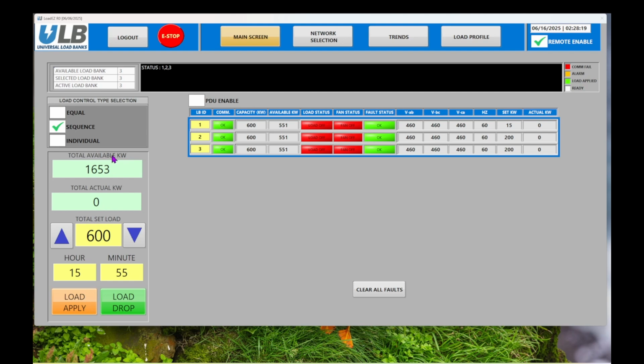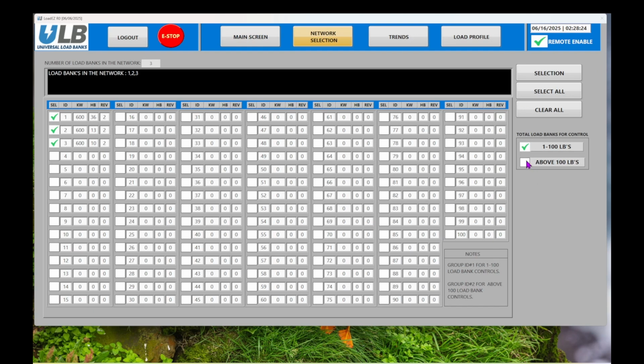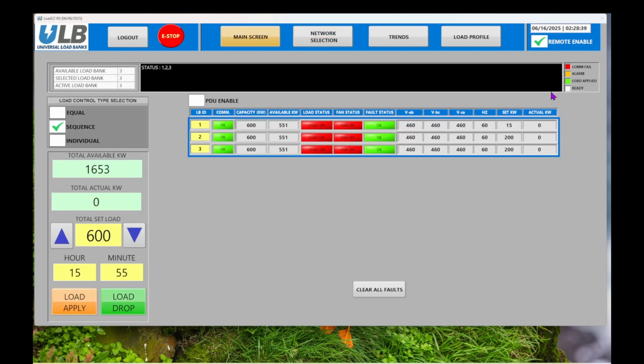If you're working with more than 100 load banks, select above 100 load banks to enable extended control. Make sure the group ID is set to 2 on the HMI for systems with over 100 units. All other operations remain the same as in single load bank mode. At the top, the status banner gives you live updates for each load bank, whether communication is successful, alarms are present, load is applied, or the unit is ready and healthy.